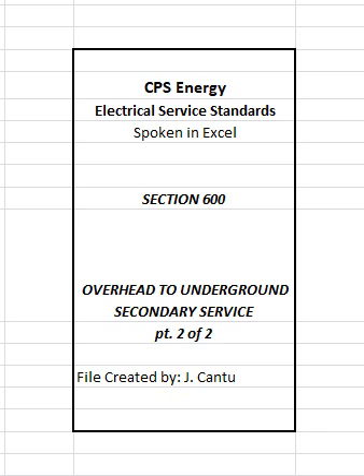604.12 CPS Energy inspections. The service trench and conduit installation must be inspected by a CPS Energy inspector prior to backfilling the trench. If flowable fill encasement is required, an inspection must be made before pouring the flowable fill and after flowable fill has been poured. City inspectors or other AHJ inspectors do not perform these inspections. To schedule an inspection, customer may contact the CPS Energy customer service representative or refer to helpful numbers listed on the inside front cover page.